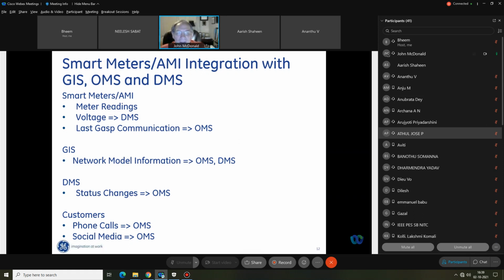Here are some examples. With smart meters, we can get the voltage from a smart meter and include that into the distribution management system in the network model. We do that when we do volt-var control, because we need to make sure the voltage at the last customer is within the range that's the standard in our country.